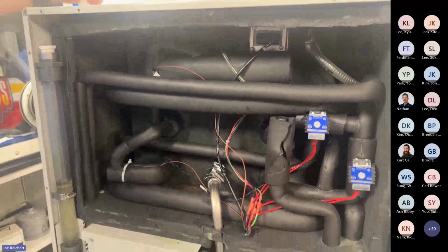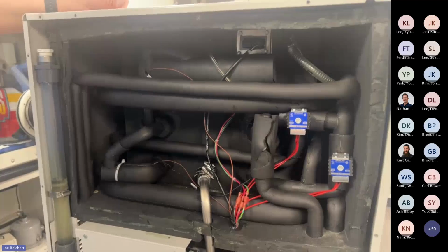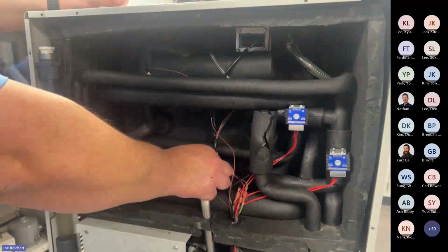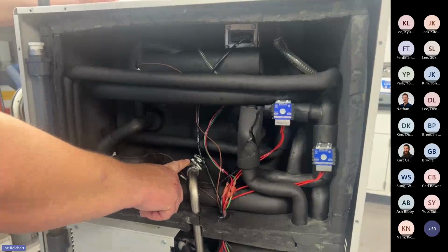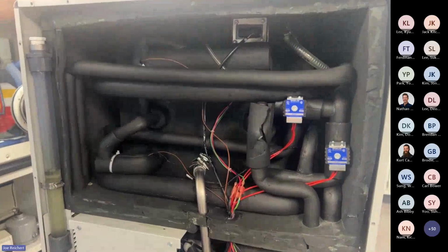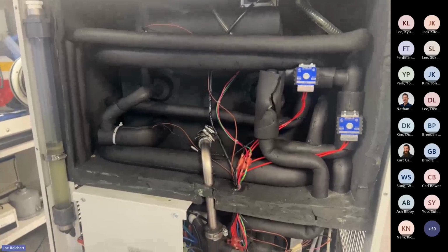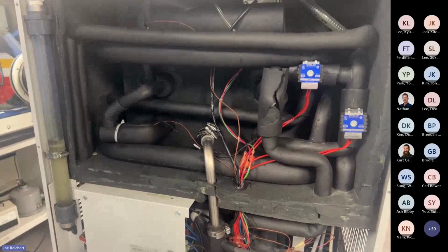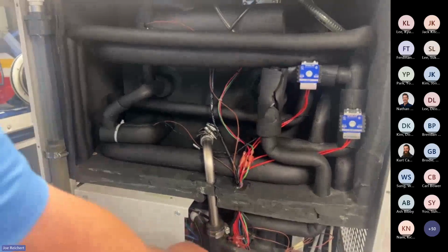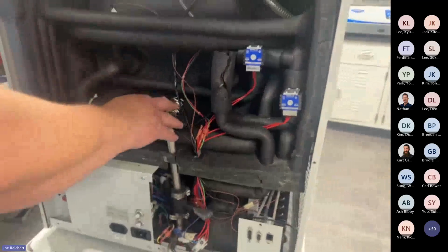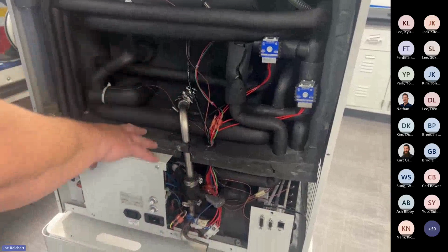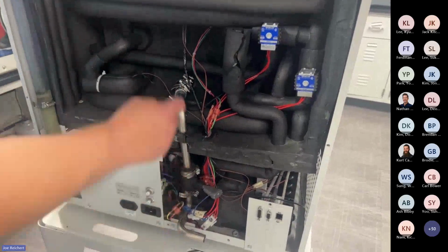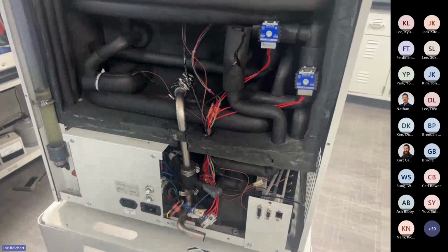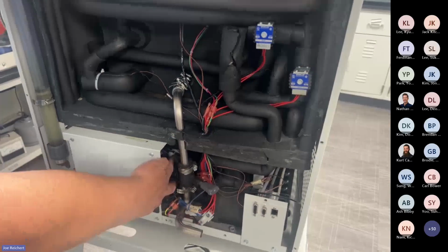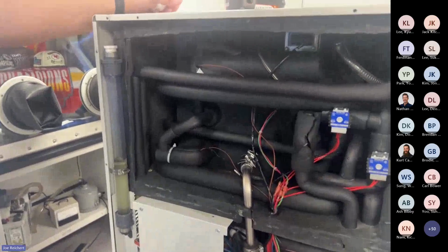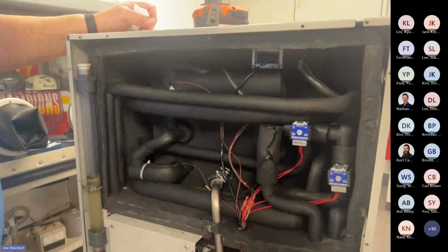I have had some where we had a vacuum leak on the unit and it took until we found out these clamps right here had gotten loose. Both clamps there were loose and allowing it to bleed air there. So that's a spot where it's possible. You hope you don't have to get inside the insulation just to find a vacuum leak. But if you block everything off from the inside and you still have a vacuum leak someplace, even after putting the stopper in the hole, then you still have this whole apparatus here of pipes and rubber coupling with your vacuum sensor, vacuum release valve back on the inside. That can still have a possible leak because you do have several clamps involved in here.